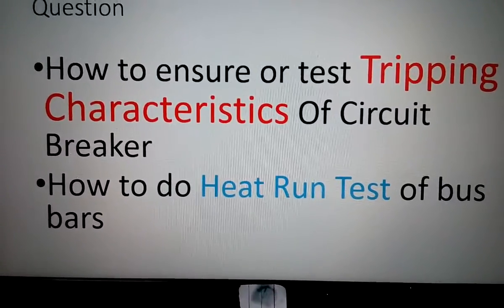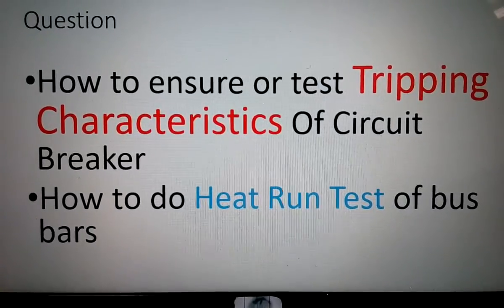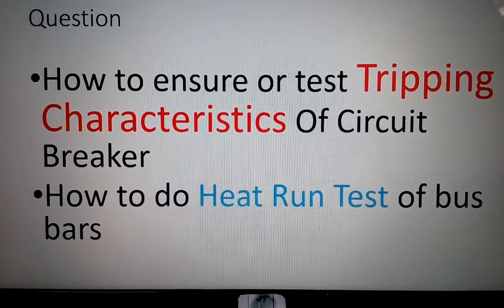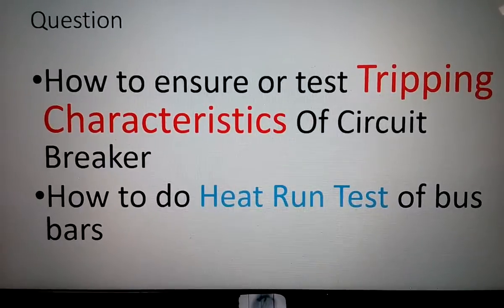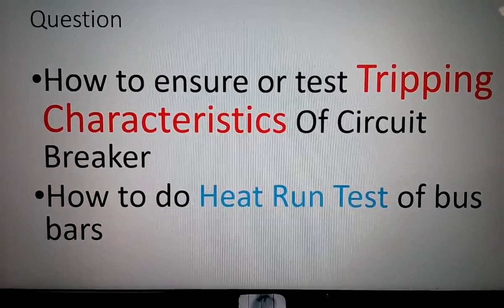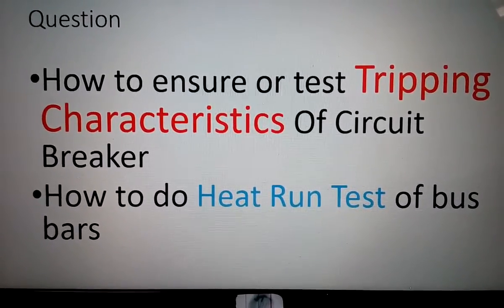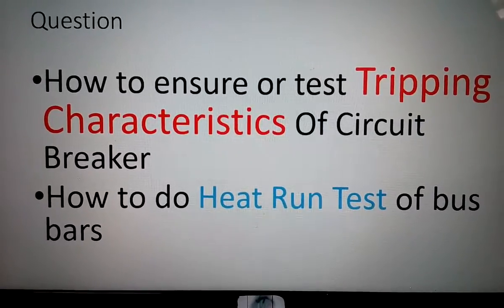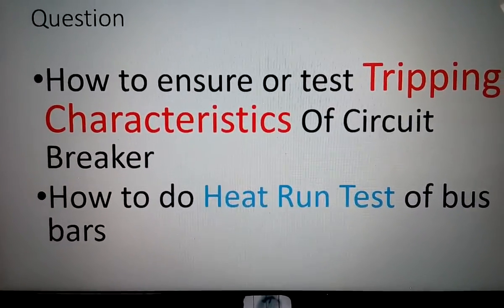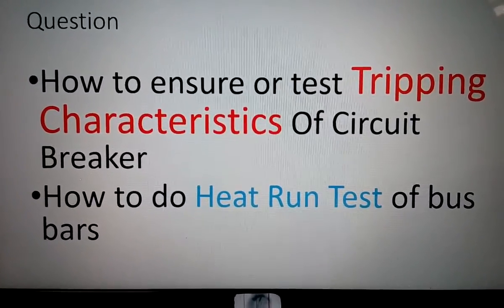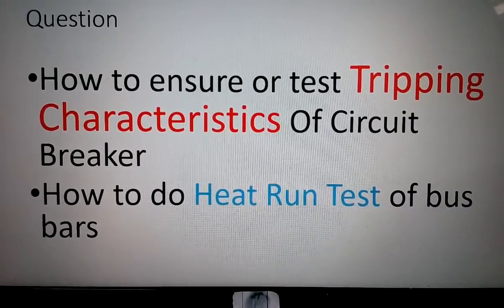So here, how we can test circuit breaker tripping characteristics and how we can see the temperature rise into the bus bar by giving the current at normal frequency, that is fundamental frequency 50 Hz.